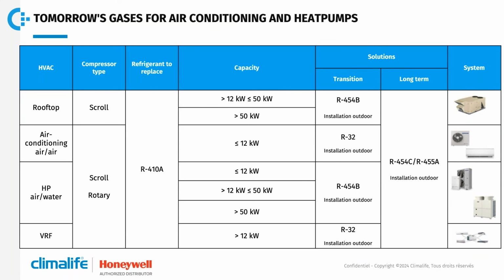So now let's see the rest of the solutions in this category. In rooftop, air systems, air-water heat pumps, and multi-split, we have R410A. In the majority of these systems, we have scroll compressors. For transition, we have two solutions, R454B or R32. For the long-term solution, it is also simple. We have R455A and R454C. So once again, solutions at less than 150 GWP are available to respond to all the necessities of a product.